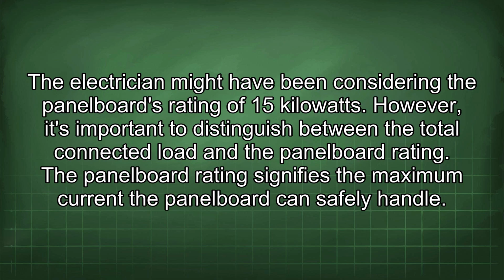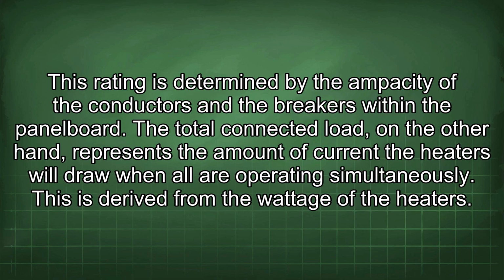The electrician might have been considering the panel board's rating of 15 kilowatts. However, it's important to distinguish between the total connected load and the panel board rating. The panel board rating signifies the maximum current a panel board can safely handle. This rating is determined by the ampacity of the conductors and the breakers within the panel board. The total connected load, on the other hand, represents the amount of current the heaters will draw when all are operating simultaneously. This is derived from the wattage of the heaters.